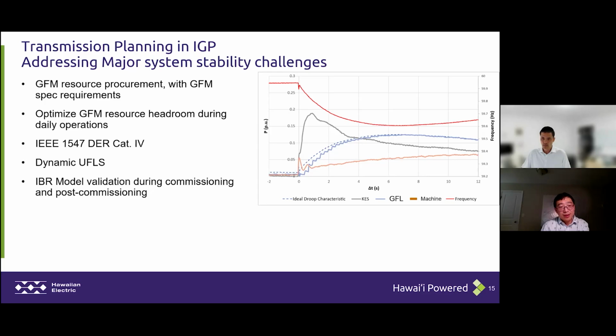This slide shows another system event, when the system has a large generation trip, which causes frequency to quickly decline. The gray curve shows our transmission-level grid-forming resource response. We also have a grid-following resource response to this under-frequency event, and the machine response. You can see that for the grid-forming resource, in the first 4 seconds or so, the output is much stronger than the other resources.